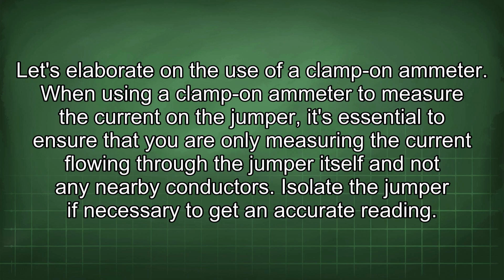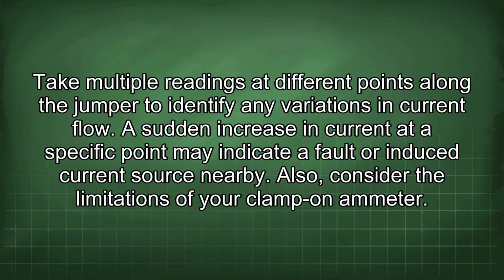When using a clamp-on ammeter to measure the current on the jumper, it's essential to ensure that you are only measuring the current flowing through the jumper itself and not any nearby conductors. Isolate the jumper if necessary to get an accurate reading. Take multiple readings at different points along the jumper to identify any variations in current flow. A sudden increase in current at a specific point may indicate a fault or induced current source nearby.